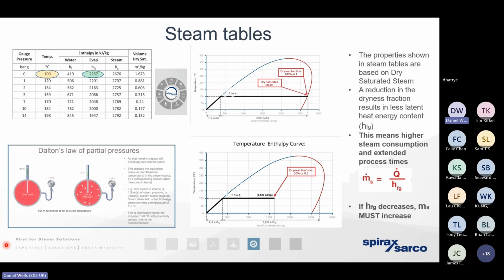I've mentioned previously that the steam tables are only 100% accurate and reliable if the steam is kept in a perfectly dry condition. Now, for reasons we've gone through in previous presentations in the series, you'll appreciate that it's nigh on impossible to guarantee that we've got steam that sits on that red dry saturated steam line all of the time. It's simply impossible because the boiler cycles, it's going to operate at different pressures, there's going to be different demand loads and so forth. So it's a very, very extreme example, but if we had steam that was 100% dry, we could rely on these values with 100% accuracy and reliability.